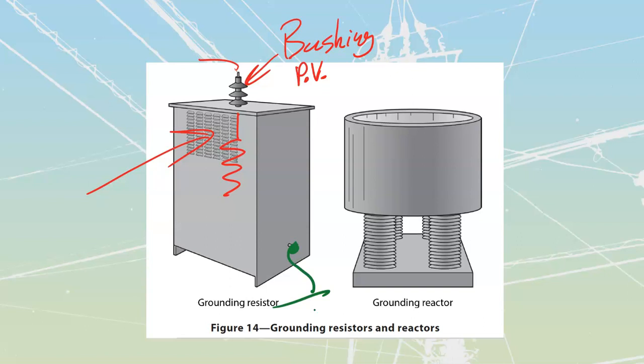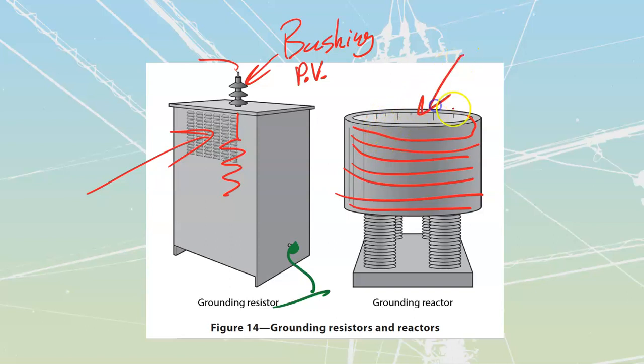The other one we're going to have is the grounding reactor. The grounding reactor is actually made up of many, many coils of large wire just wrapped around. Sometimes you'll see the coils, other times they place shielding around them, but usually they're hollow cylindrical structures so we can get maximum airflow onto these things. They isolate the entire thing from ground, usually because they do a couple of up-down windings to keep them spaced.